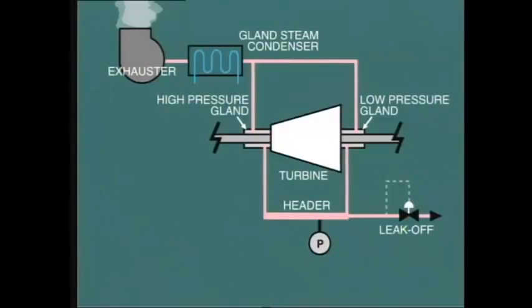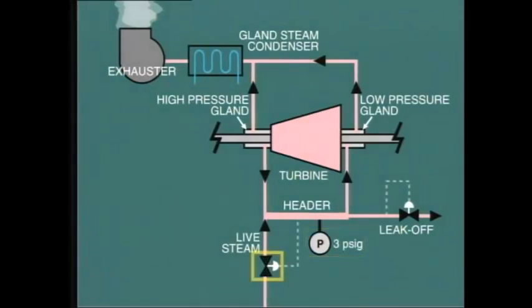But how does the system work when we're preparing for startup? In this situation, we need to pull a vacuum in the turbine and condenser before admitting any steam into the turbine. So in this condition, we have no leak-off steam. Instead, live steam is supplied to the gland steam header. The live steam supply valve is set to control the header pressure at about 3 psi to coordinate its operation with the leak-off valve. When the turbine comes on load, the leak-off steam from the high-pressure gland feeds into the header and so raises its pressure. When the pressure gets to 3 psi, the live steam supply valve will close. When the pressure rises to 5 psi, the leak-off valve will open enough to maintain this pressure.